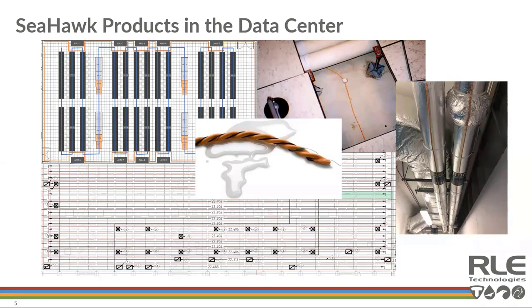So it doesn't have to be a raised floor application for leak detection to be an applicable product. Some of the larger sites, referred to as hyperscale data centers, I've seen some of those sites that require more than 50,000 feet of sensing cable in a single site. So certainly the opportunities and the applications, and certainly the opportunities for large purchase orders, are out there with some of those sites.